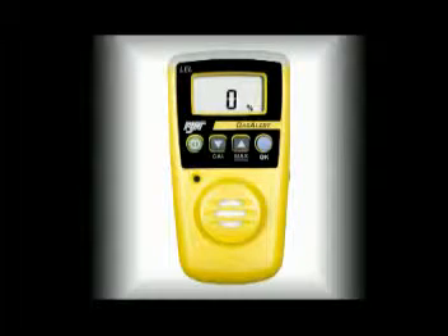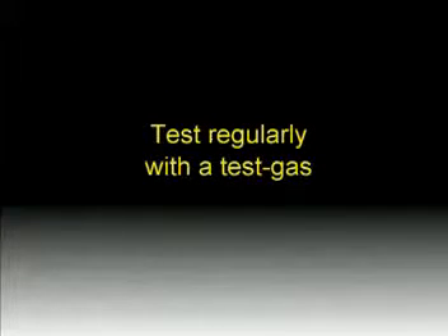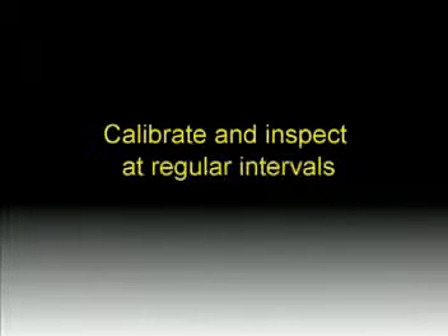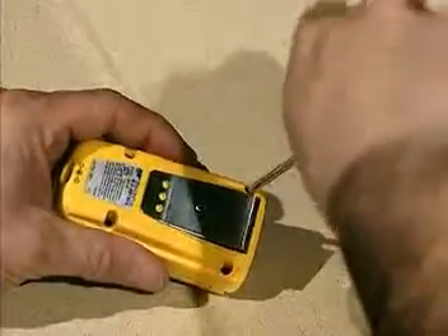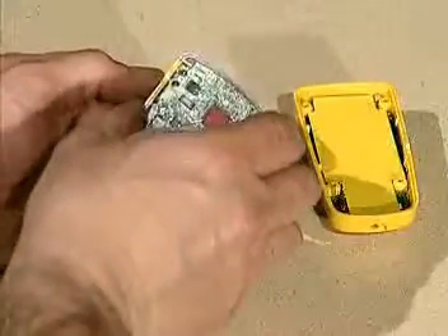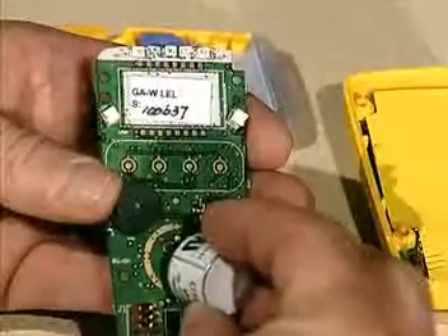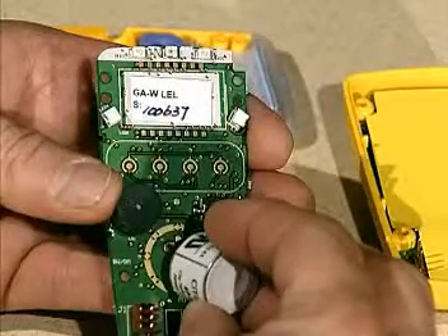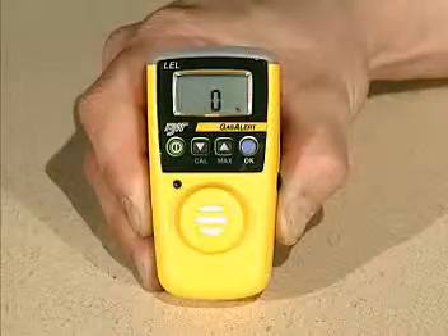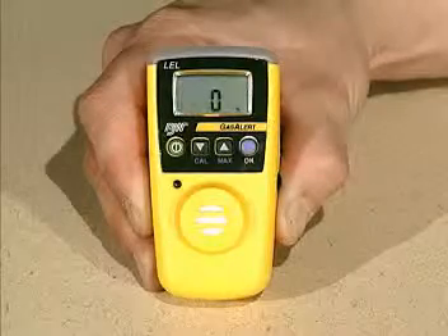Your GasAlert-LEL will provide years of service with only minimal maintenance, but any sensor may become plugged with dirt or debris. To ensure the sensor responds to gas, routinely test it with a test gas. Calibrate and inspect your detector at regular intervals. To replace the battery or sensor, remove the back cover. The plug-in sensor provides consistent and accurate ambient gas readings. We have now covered the operation and basic care of the GasAlert-LEL.